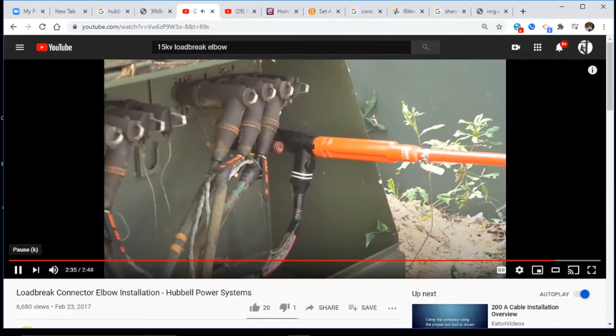When the wrench permanently deforms at approximately 100 to 200 inch-pounds of force, attach a number 14 AWG copper wire to the grounding eye of the elbow. Twist the wire at least 2 turns. Attach the free end to the system ground. Okay, this is going to be coming up also on a quiz later on.